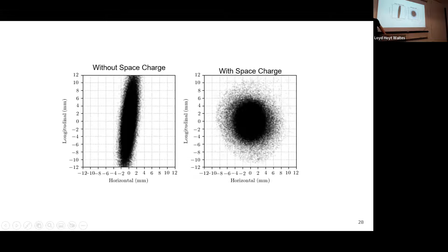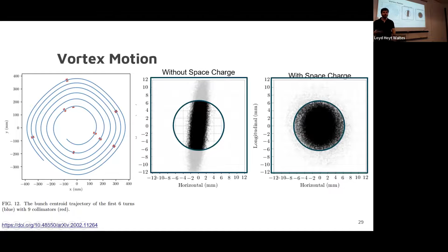And why this is so important, as you can imagine, going through the actual cyclotron, you have these things called collimators. And these collimators clean up the edges of the beam to make sure that you're only getting this nice round extraction in your beam. And this is kind of a profile of the beam that's going to be lost in those collimators. You can see there's not a very clean extraction here. You get a lot of cut and you don't have a nice round circle, whereas here you have a nice round beam that's going to limit any kind of radiation that's going to occur inside of the cyclotron.